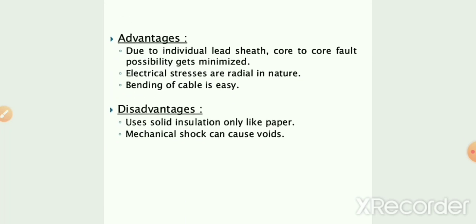An advantage of the high voltage power cable is that due to individual lead sheaths, the core to core fault possibility is minimized. The electrical stresses are radial in nature, and bending of the cable is very easy. A disadvantage of the power cable is that it uses solid insulation like paper, and mechanical shock can cause voids.